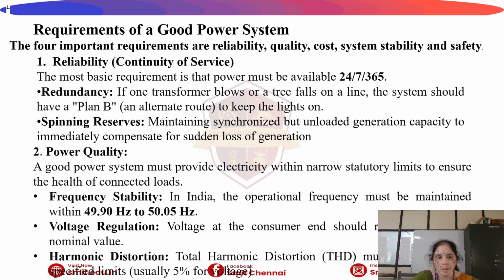The second important requirement is power quality. A good power system must provide electricity within a narrow statutory limit to ensure the health of connected loads. Frequency stability: in India, the operating frequency must be maintained within 49.9 to 50.05 Hz. Voltage regulation at the consumer end should be maintained at a nominal value. Harmonic distortion should usually be limited to 5% of the voltage. The total harmonic distortion should be minimum.